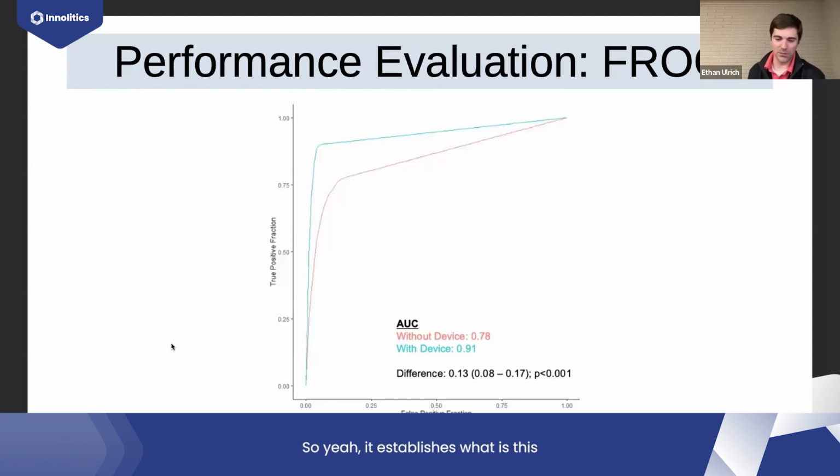So yeah, it establishes the baseline performance of your device, how good it is at detecting these lesions, and it removes that human element. So that is also included in a submission. I did have a small section related to it in that protocol that I created, but it does need a little bit of work to finish that out. But yeah, that's a good question. This is really just one side of the coin for the clinical performance assessment. There should also be an evaluation of the device itself.